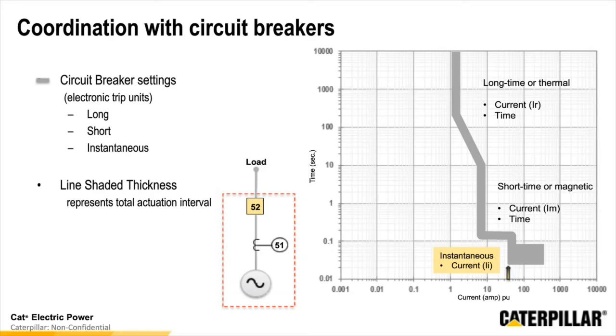Now, something else you'll notice different about the breakers rather than the relay settings is that there's a shaded line thickness here. The thickness that we're seeing in the line actually represents the full period of the actuation of the breaker. This is the identifying of the fault that's occurring. This is the physical opening of the breaker and extinguishing the fault within the system and the current that's flowing through it. This also takes into account the variability in manufacturing of breakers, and that not all breakers are manufactured exactly the same. So there's going to be a little bit of variability overall for the different breakers, and you take that into account with this shaded region.